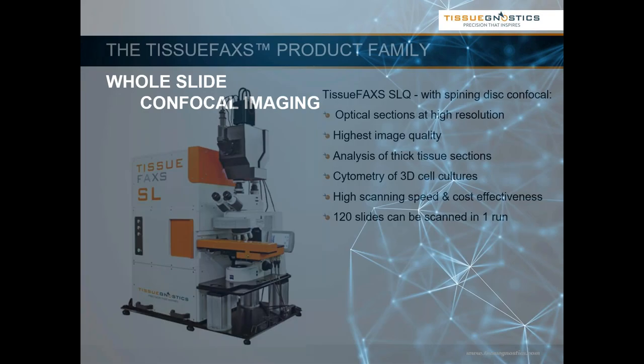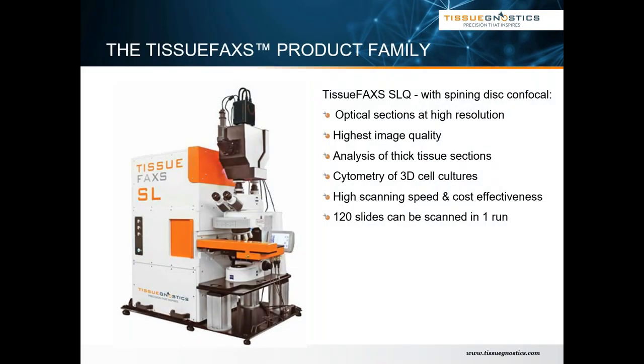Another configuration that these systems can be built with is a confocal spinning disc. That's made possible by the TissueFAXS software and workflow, which enables the capability to extend even to confocal scanning. So we can do optical sections and define the thickness of those optical sections. You can combine the system with a 120-slide loading system — an automated slide loader. You can scan up to 120 slides in one run, scanning bright field, fluorescence, or wide field fluorescence and confocal slides in the same run. You can also color-code samples and let it run over the night or over the weekend, and come back the next day to have 120 digitized slides.